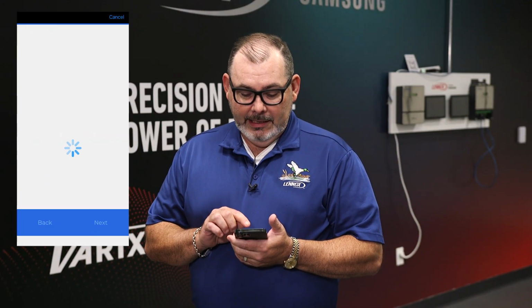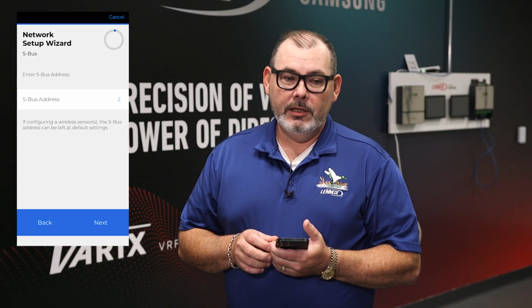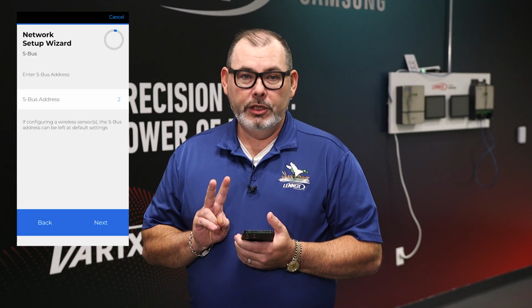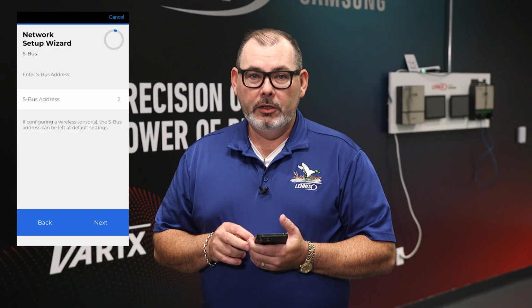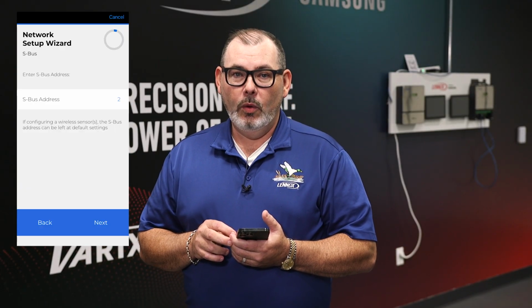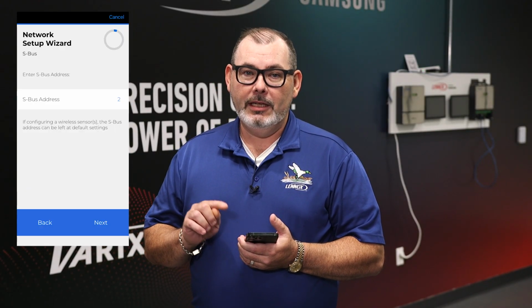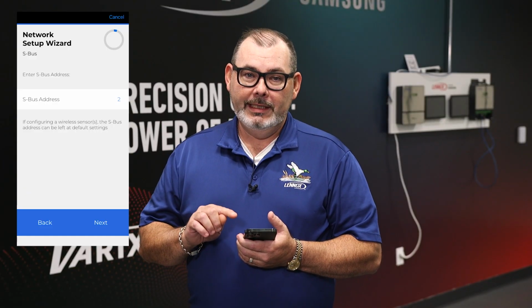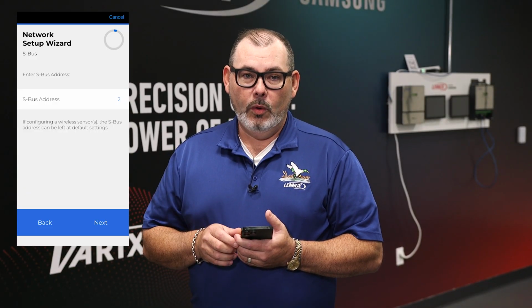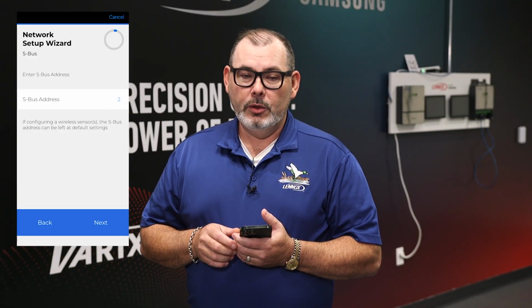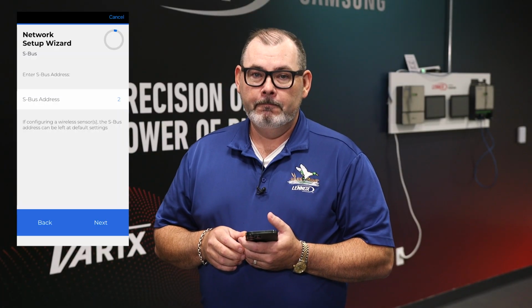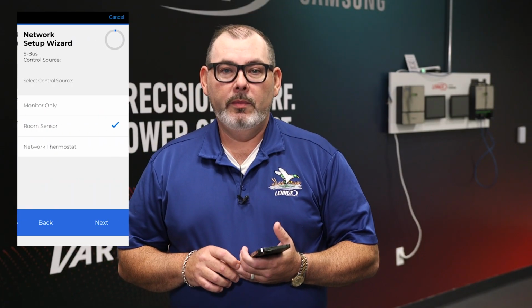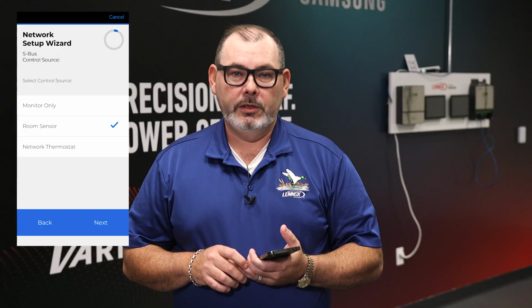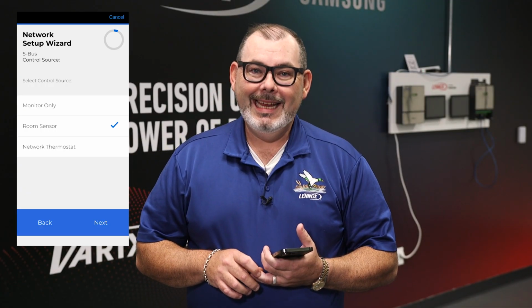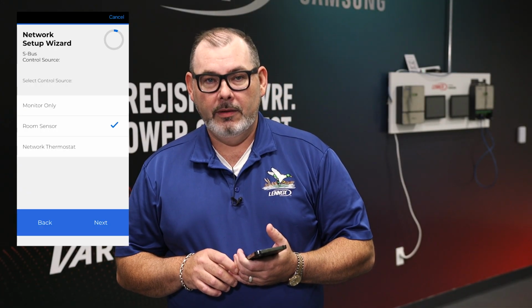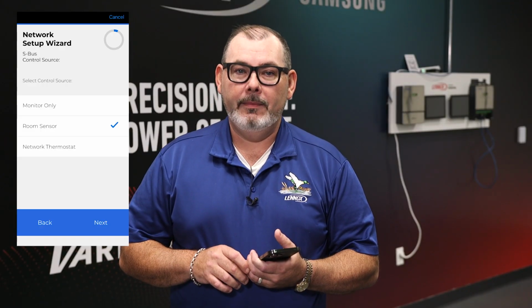Now we will go and select your address. Your default address will be set for 2. When working on RTUs, you can use the default address, or you can continue to select and match your RTU number on your CS8500 and your core. They will need to match or they will not communicate. After you've selected the correct address, we will move forward to selecting your control source. Your control source will need to be selected as room sensor. After you've selected room sensor, tap next.